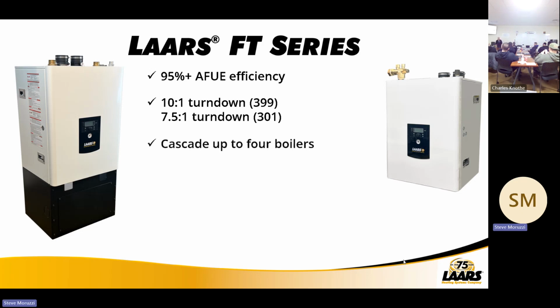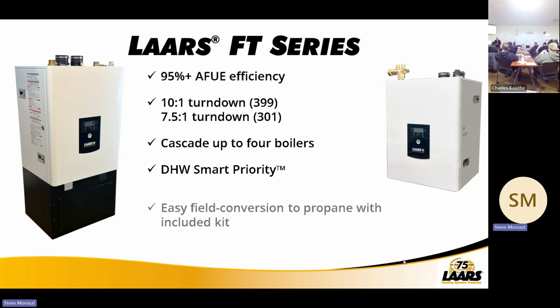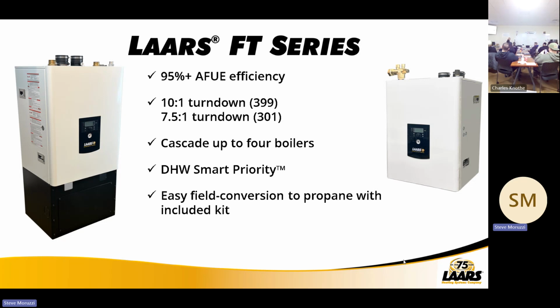Right? We can cascade up to 4 of these boilers. These are not combis, by the way. This is heat only. If you needed volume water heating, you would add an indirect tank. All right. We still have that smart priority. That's 80% of modulation. We want to shut off that system pump and provide heat to the domestic as needed. And again, one of the easiest products to convert to propane, less than 4 minutes in the field. No secret handshake with the programming or all of that. You replace the orifice and you take your dip switch and put that to the propane position. Again, wall hung or floor standing.